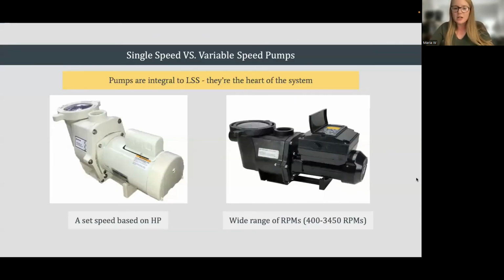Pumps are super integral to the LSS—they are basically the heart of the system. Without a pump, you're not going to do anything. These can be very expensive in terms of life support equipment, or a little bit cheaper, but unfortunately they go through a lot of hard times. They get used 24/7, they never stop unless you tell them to, or they die. So you need a lot of maintenance and care on these to keep them running, because we really need them to run for our facilities.